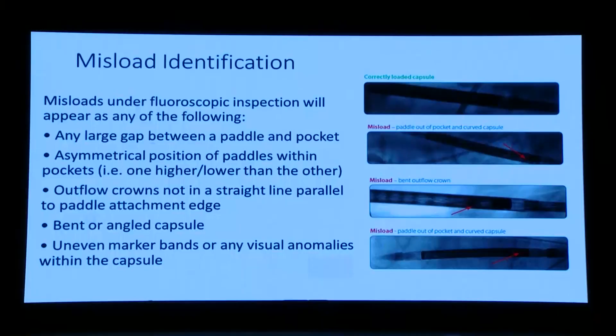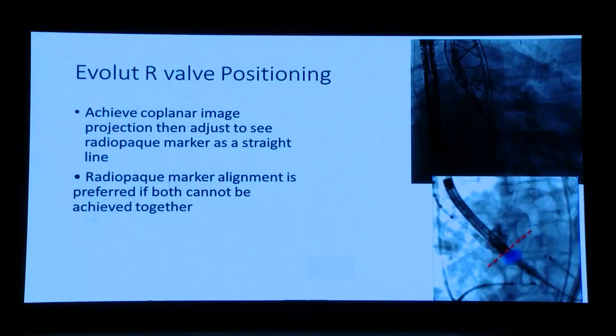Once we do that, then you achieve the coplanar image, again removing the parallax. Again, you can see there's a circular. I hope you can see that. We change the position, make it more caudal to make sure that the circle is in a single line, which ensures that it's in the coplanar position. That's called removing the parallax. Once we remove the parallax, we are now coplanar. Then we start. Once the valve is entering the LV, we slowly start releasing the valve.